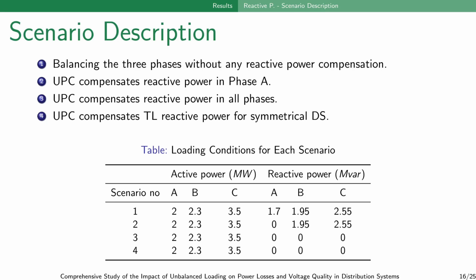Scenario description. The first scenario is balancing the three phases without any reactive power compensation, while the second scenario is compensating the reactive power only in phase A, and the third is compensating the reactive power in all phases, while the last one is not only compensating in all phases but also compensating in the transmission line. And this table shows how the reactive power differs in each scenario.